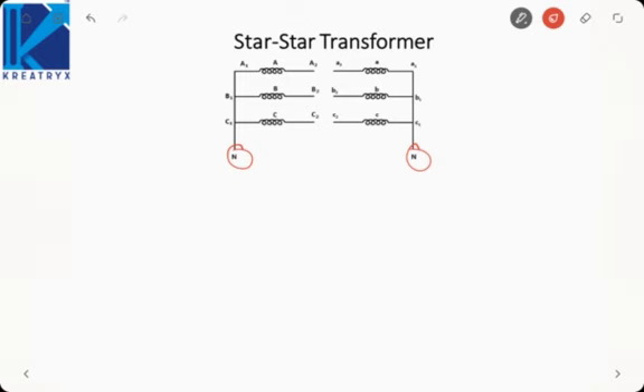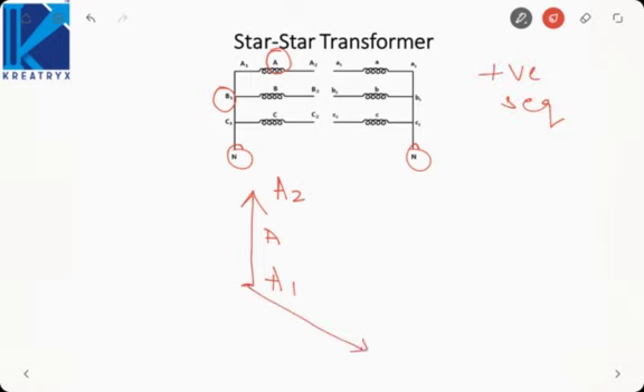Again first we will draw the primary phasor and based on that we will draw the secondary phasor. As I told you, this A phase on the primary must always be vertical so that this can be used as a reference phasor to determine the phase shift. So I will draw like this. This will be my A1, this will be A2. Now A1 is connected to B1. Okay, this point is connected to B1 and this phase is A. So B phase will be 120 degree lagging, assuming positive sequence. So it will be like this. This is B1, this will be B2. Now C phase will be 120 degree lagging like this. C2, this will be C1. All these points are neutral.